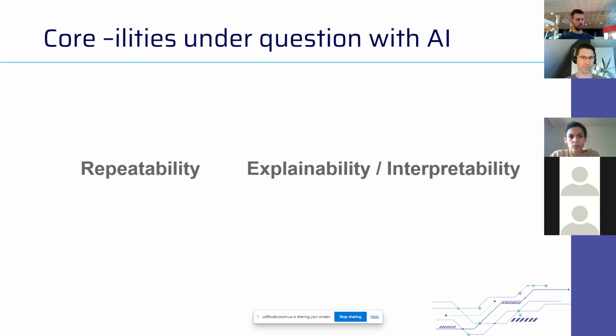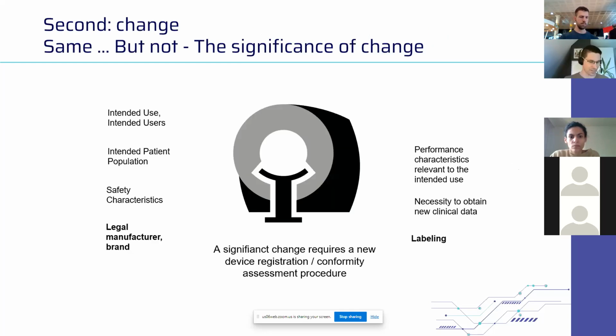And then there is the interesting discussion with the Draft AI Act. Article 43, Section 3 or 5, I'm still not so firm on this one, says, using FDA terminology in a European document, that if there is a predetermined change plan, any change of the product that it's doing by itself under the conditions of the plan is not a substantial change. Now, the word substantial comes from FDA. It needs to be understood as significant change in European terms. But what would that imply?